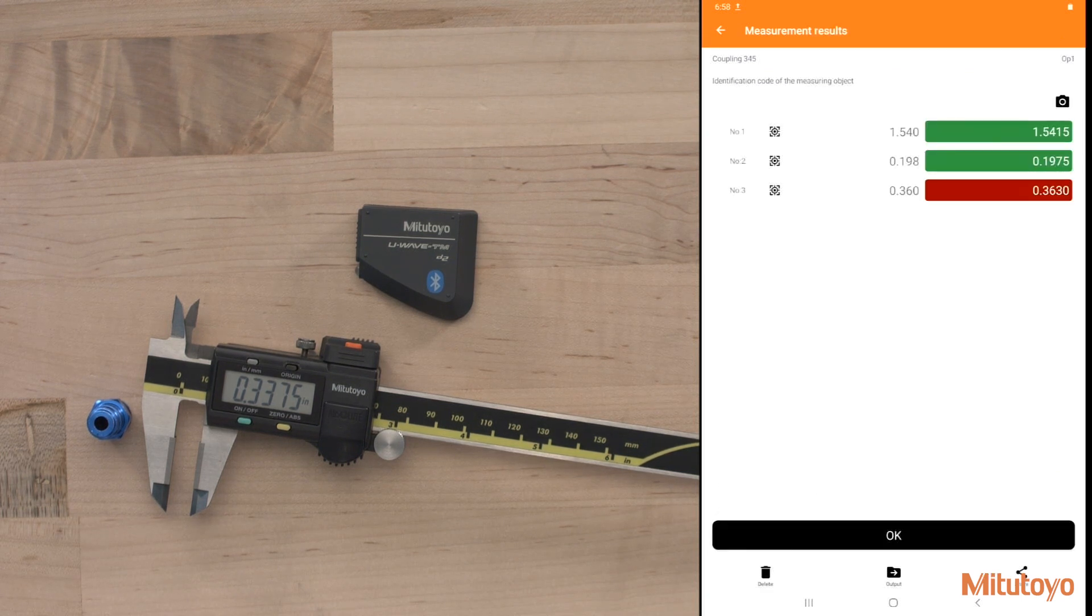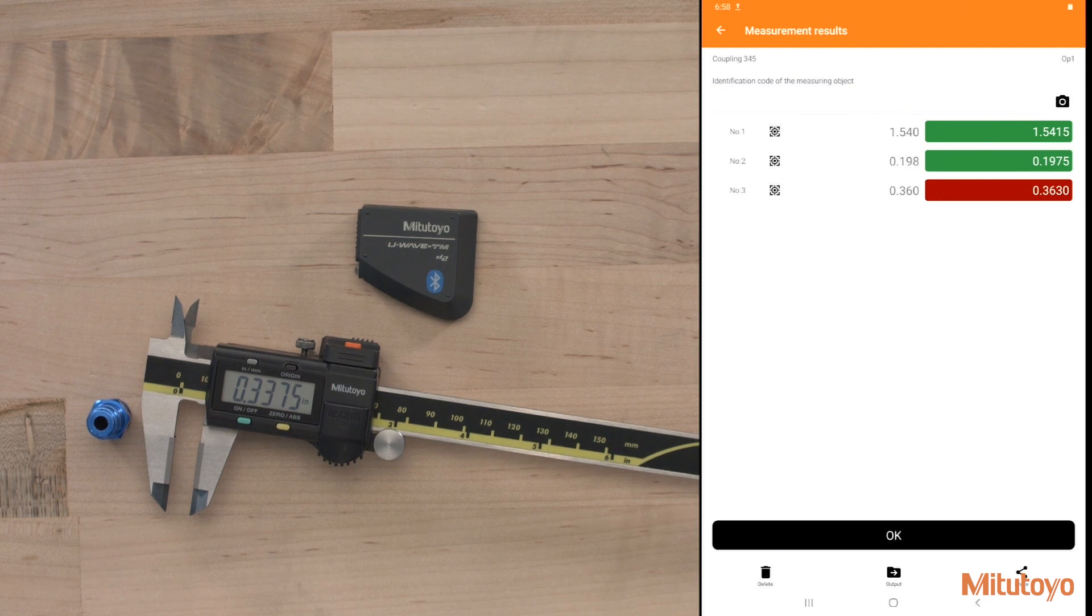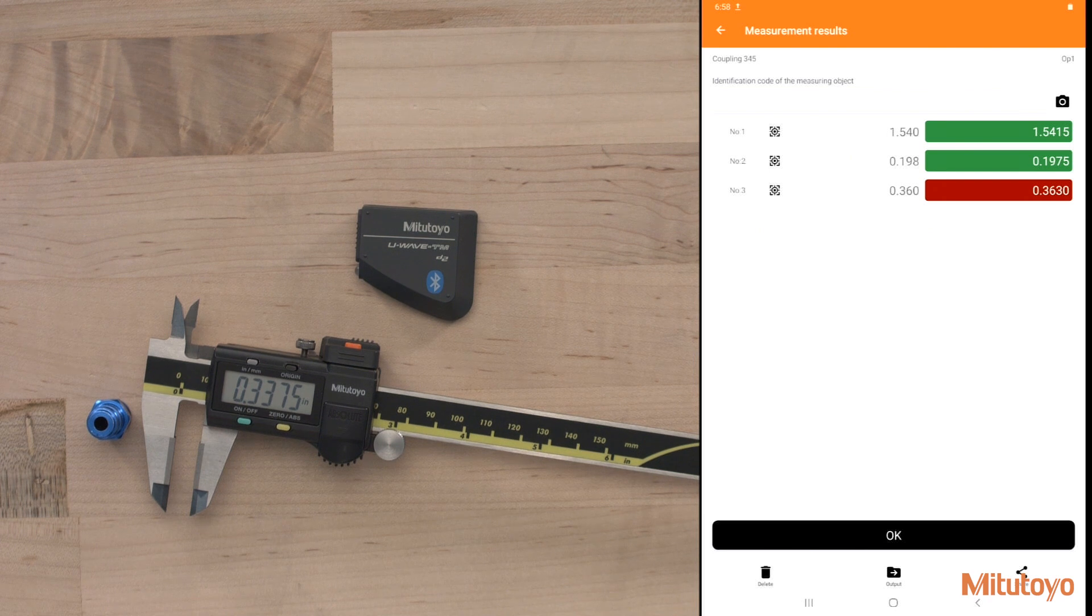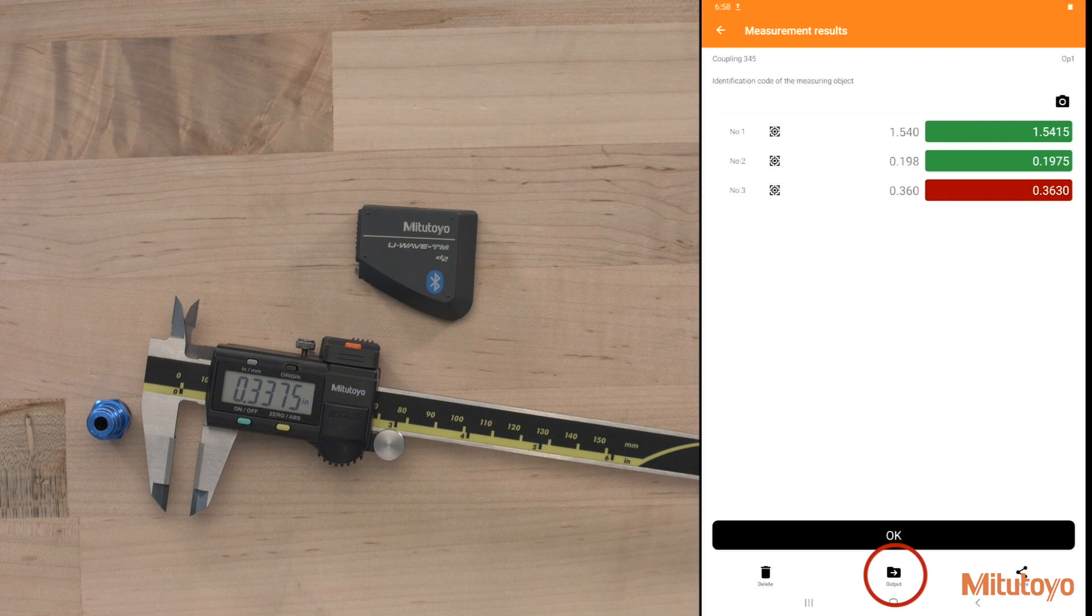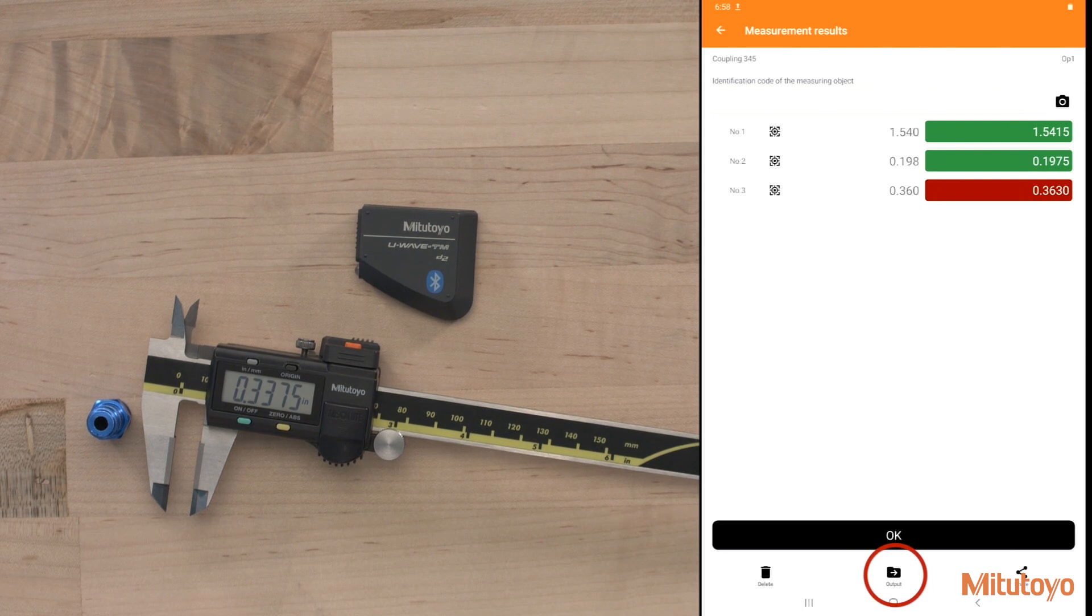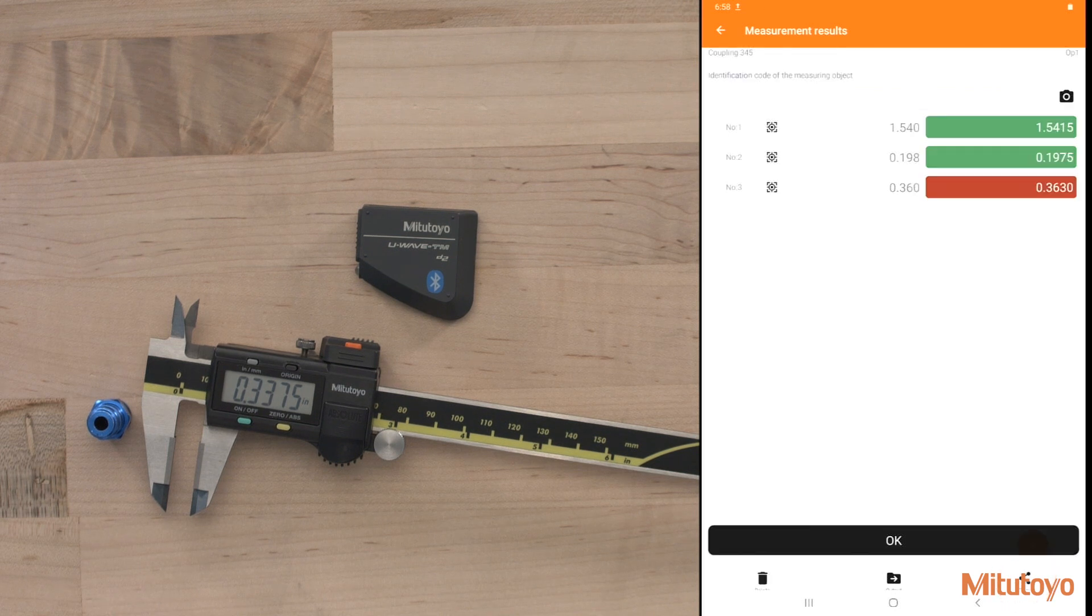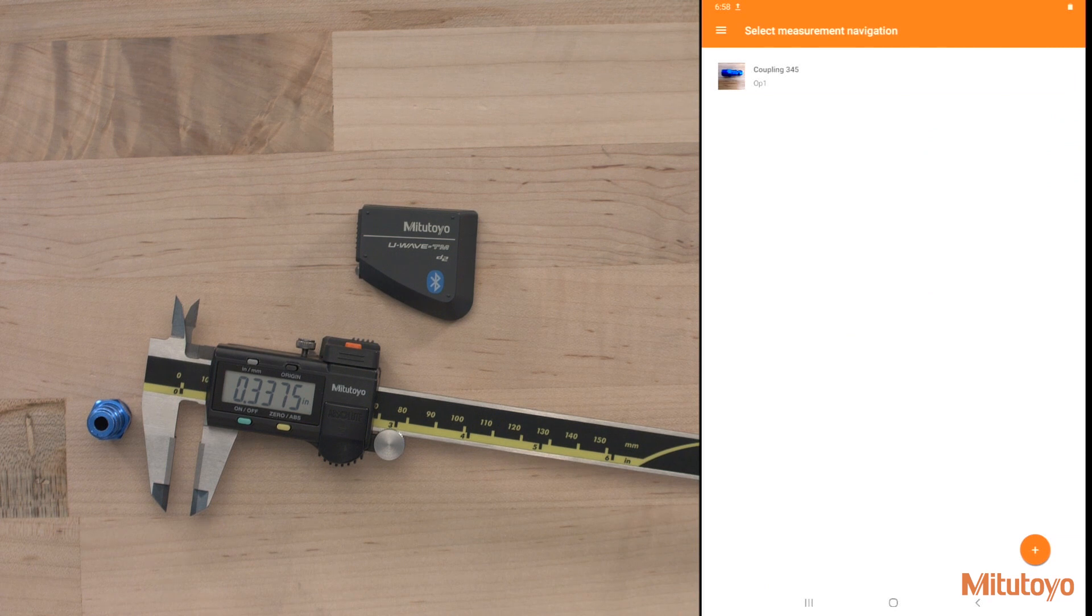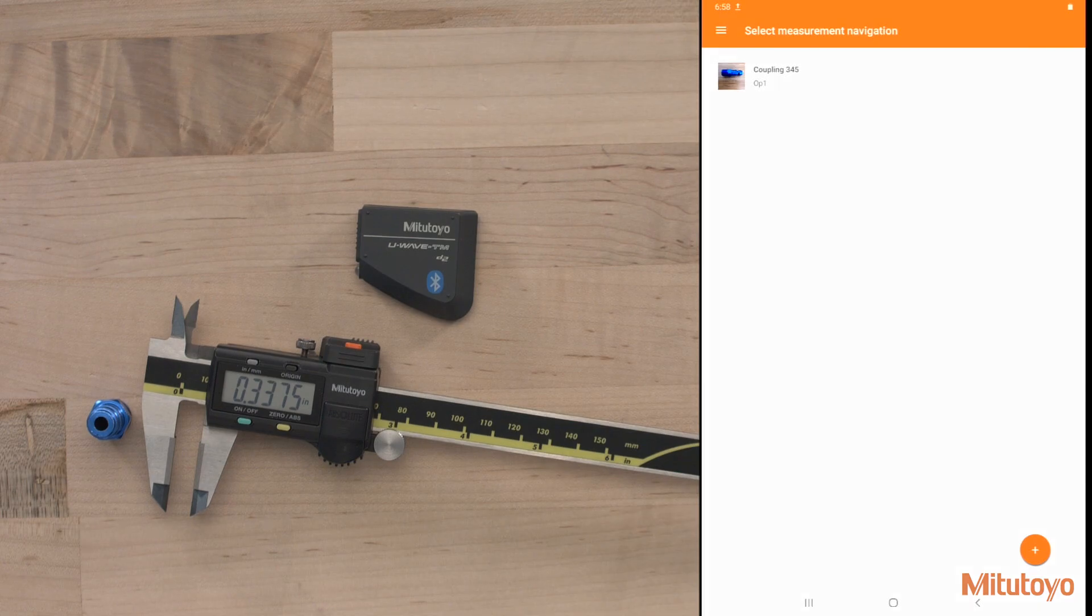At the end here, we can see all the measurement results, things that went out of spec and went in spec. I can add an identification code or a serial number to my part. And I can use it to take a picture as well. On the bottom here, I have an output or a share function as well that I can go ahead and share my data with a PC or with anyone who needs it. I can press OK to finish. And I'll return back to the measurement navigation screen where I can continue to take more measurements.